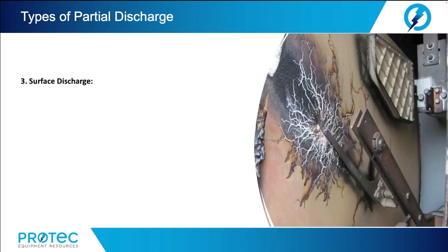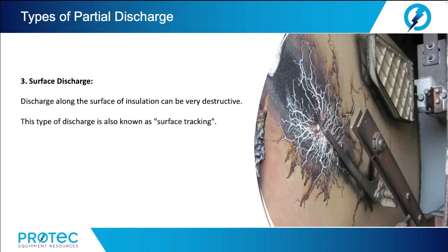And that brings us to number 3, surface discharge. Discharge along the surface of insulation can be very destructive. This type of discharge is known as surface tracking, usually caused by contamination or weathering of insulator surfaces. It is different from corona because it tends to track to ground metal. Corona discharges to water molecules in the air. Corona conditions can evolve into surface PD as surface contamination worsens and the discharges become more severe.